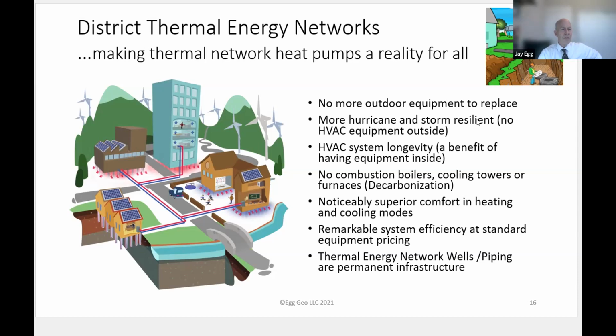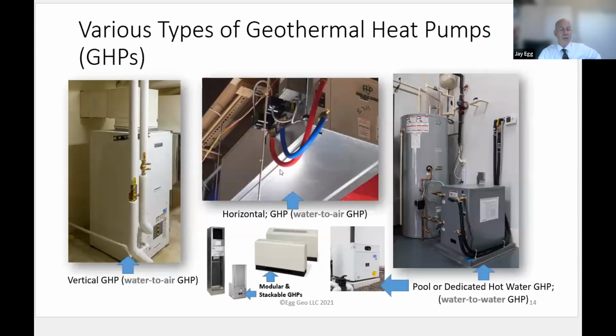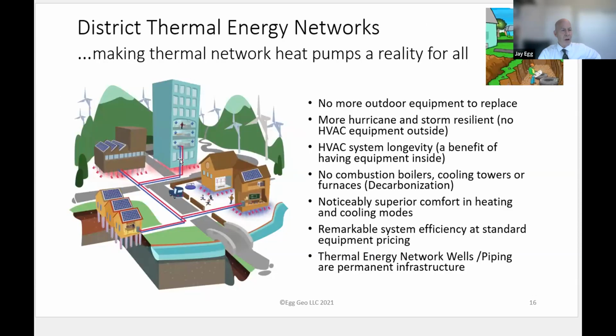And with these types of systems, the beautiful thing is there's no more outdoor equipment to replace or to see or to have to service. They are more hurricane and storm resistant because there's nothing outside that can be hurt by the elements and blown away. They have a longer lifespan because there's nothing outside to weather. They eliminate the combustion component that is normally needed with boilers and furnaces. They eliminate cooling towers, which are normally needed to exhaust heat from buildings. They have noticeably superior comfort in both the heating and cooling modes, and there is remarkable system efficiency at standard equipment pricing. These heat pumps we're talking about here don't typically cost any more than a standard air source heat pump. They simply require this infrastructure to be put in first.